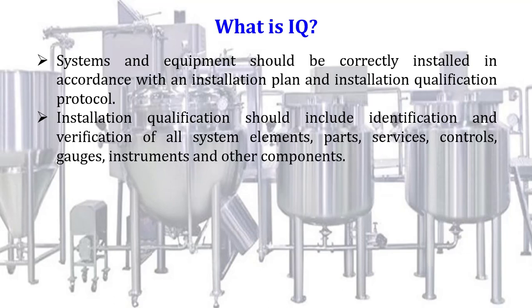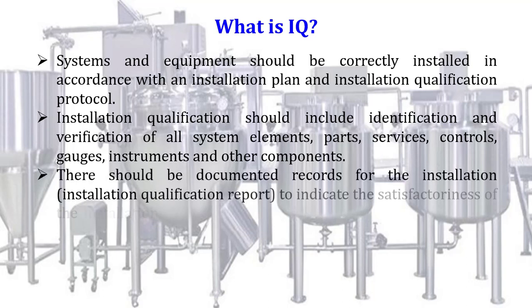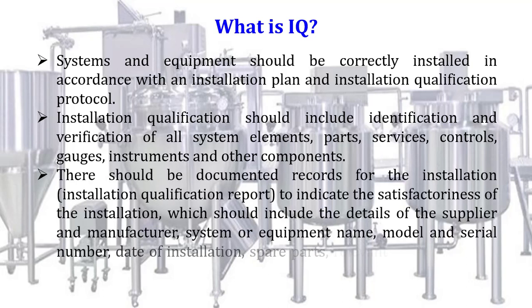Installation qualification should include identification and verification of all the system elements, parts, services, controls, gauges, instruments and other components. There should be documented records for the installation qualification report to indicate the satisfactoriness of the installation, which should include the details of the supplier and manufacturer, system or equipment name, model and serial number, and date of installation.